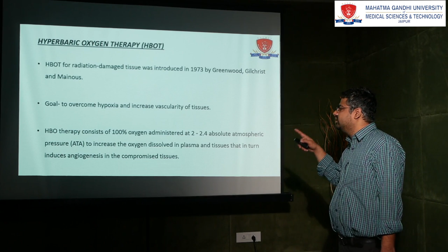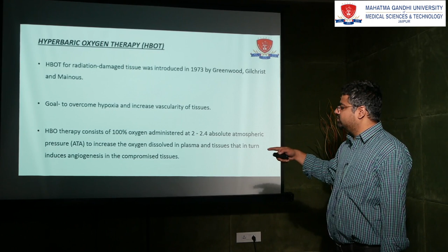Hyperbaric oxygen therapy consists of 100% oxygen at 2 to 2.4 absolute atmospheric pressure to increase the oxygen dissolved in plasma and tissue, which in turn induces angiogenesis in the compromised tissue. Method: this is the chamber where we put the patient. It is accomplished by having the patient breathe 100% oxygen through a tight-fitted mask, hood or endotracheal tube in a pressure-tolerant chamber, either alone in a monoplace chamber or with more than one patient, or a therapist, in a multiplace chamber pressurized to 2 to 2.4 atmospheres.